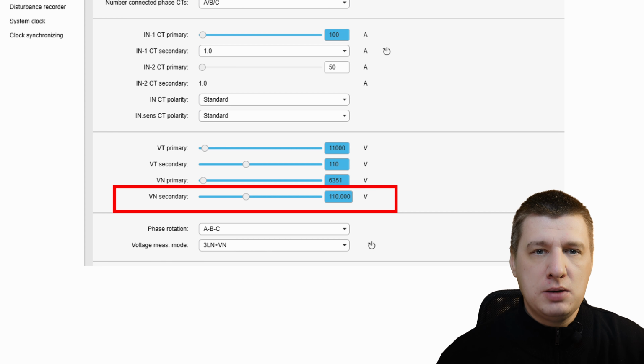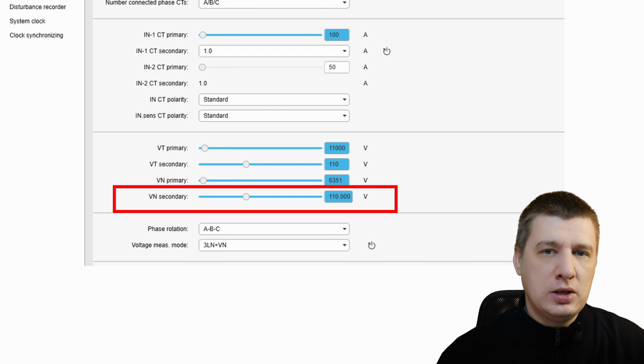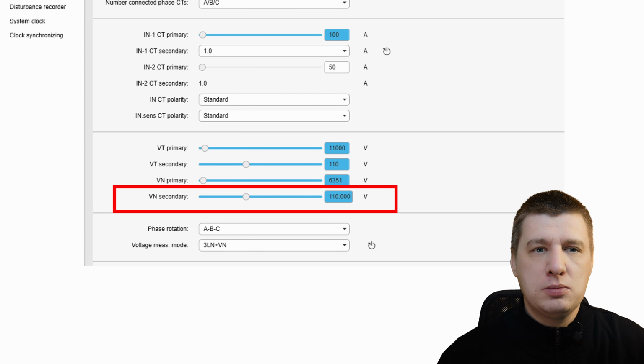If your system has a primary neutral displacement of 6.35 kilovolts and your VT steps that down to 110 volts, you will set your VN secondary to 110 volts. The relay uses this value as the 100% reference. If the relay measures exactly 110 volts at the terminals, it looks at the setting and says, okay, I'm seeing exactly 1 per unit of the rated neutral displacement. This anchor allows your ANSI protection to decide exactly when the ground fault occurred.